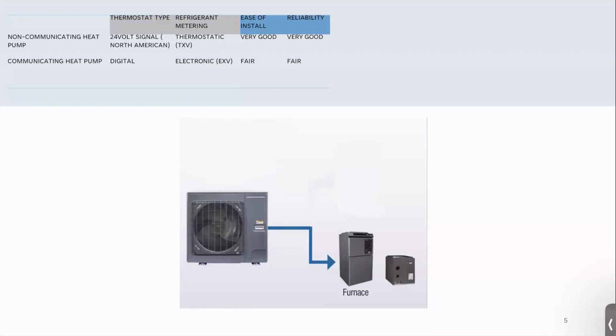And then reliability, I would say they're very similar. It's just getting to understand how they actually function and understanding the service. We have a learning curve right now on all sorts of technology. Efficiency, a slight curve ahead on the communicating because everything is working in tandem. The electricity usage is harvested very, very well. The thermostat is always speaking to the outdoor heat pump, and it's always speaking to the indoor furnace. And so everything is monitored, whereas a non-communicating system is controlled by temperature. So it's just sending temperature back to the compressor and understanding how that's running. It's very simple. The HSPF factor, which is heating seasonal performance factor, we can find slightly better on a communicating heat pump as well.